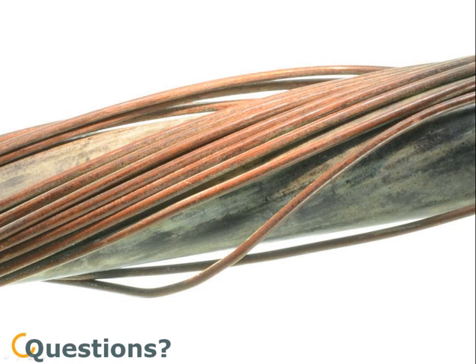Chris wants to know what effect the geometry of the neutrals has on corrosion — do cables with more smaller wires, like angel hair, tend to suffer from corrosion worse than cables with fewer larger wires of the same neutral cross-section? Smaller bleed wire type conductors would have a much larger surface area per unit volume of conductor, so they would theoretically be more susceptible to corrosion. But also, when those really small wires are used, they usually were used in jacketed cables. In general, the bigger the wire, the less susceptible it would be to corrosion.